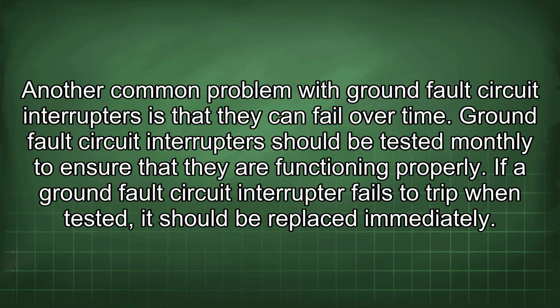Another common problem with ground fault circuit interrupters is that they can fail over time. Ground fault circuit interrupters should be tested monthly to ensure that they are functioning properly. If a ground fault circuit interrupter fails to trip when tested, it should be replaced immediately.